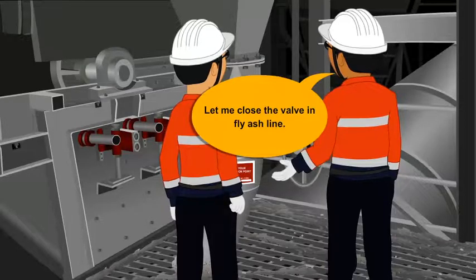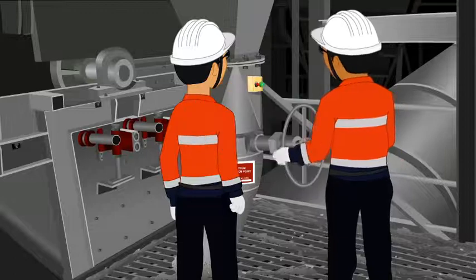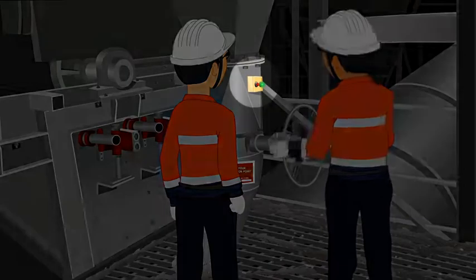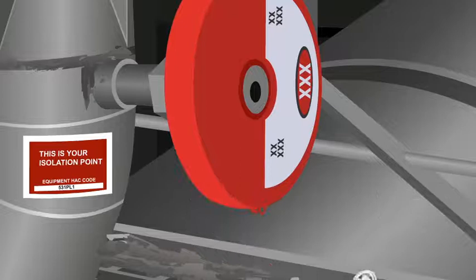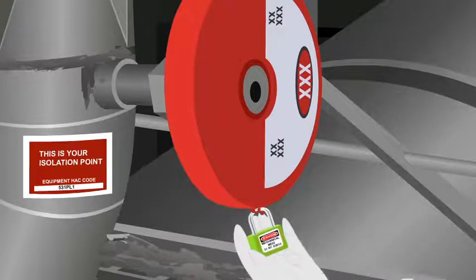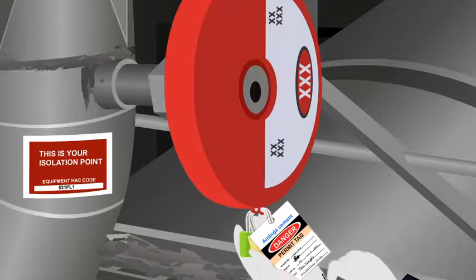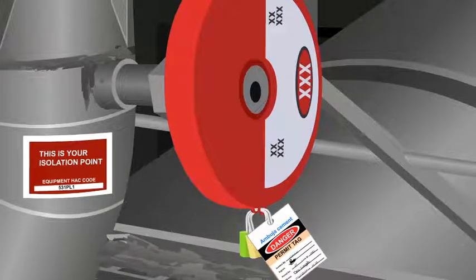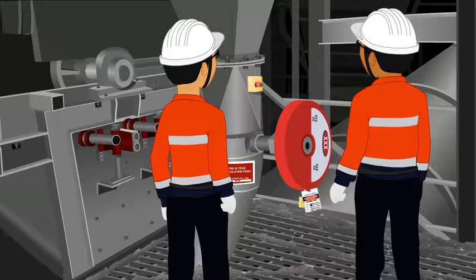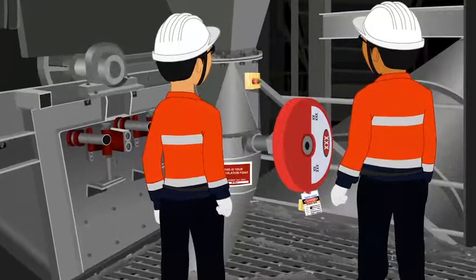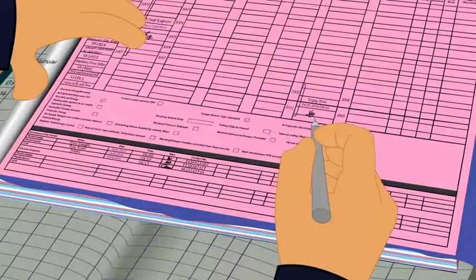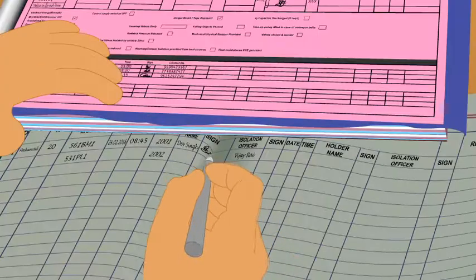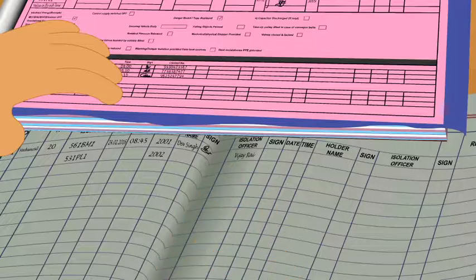VJ closes the valve on the fly ash line, attaches the isolating device, and applies his green lock. Dev then applies his yellow lock and attaches a permit tag. Dev gets the remaining relevant energy isolations completed in a similar way. VJ signs on the permit and Dev signs on the energy isolation register.